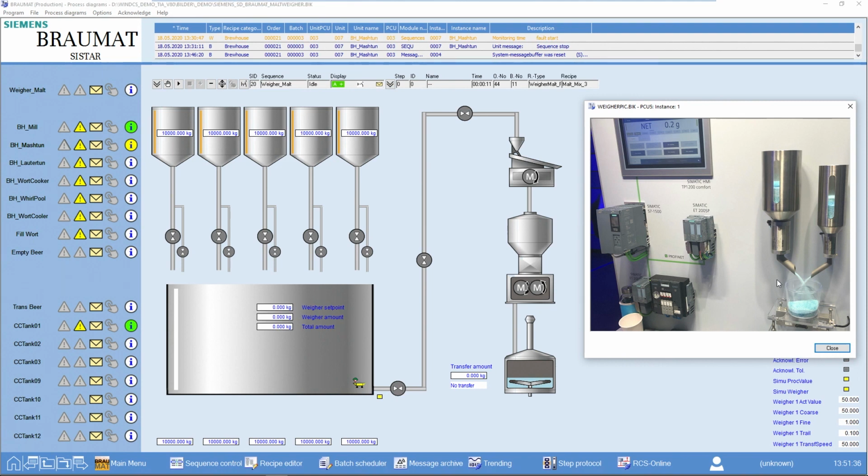There is, for example, the attribute coarse flow and fine flow cutoff, i.e. large and small valves are being switched off when a relative set point is reached, i.e. shortly before the final value of the installation is reached. Furthermore, there are tolerance values, i.e. values which allow to make this weighing correspondingly exact or inaccurate. Every time a component change occurs, these corresponding attributes are also loaded into the SIWAREX scale.